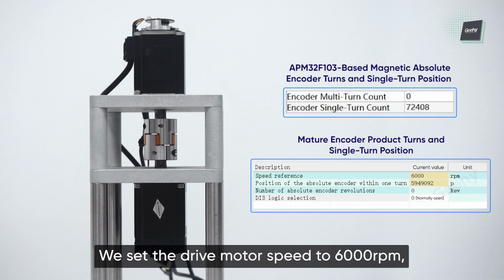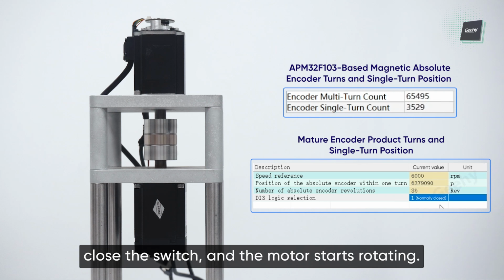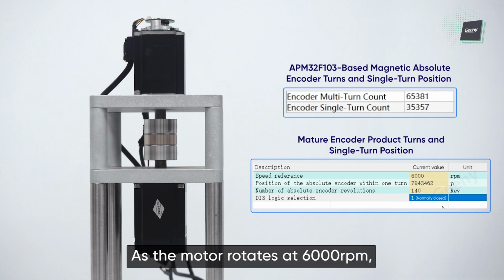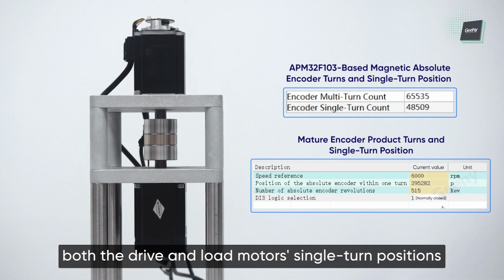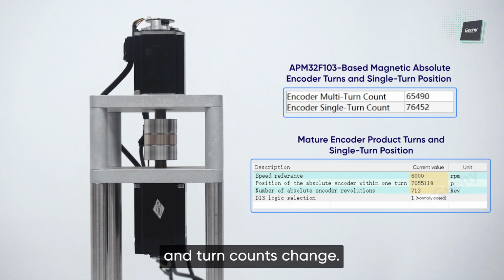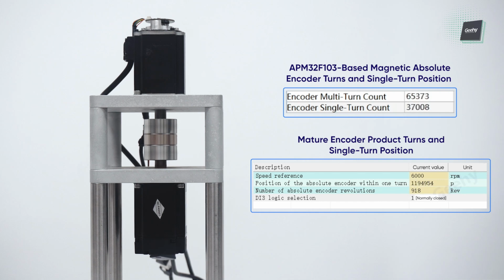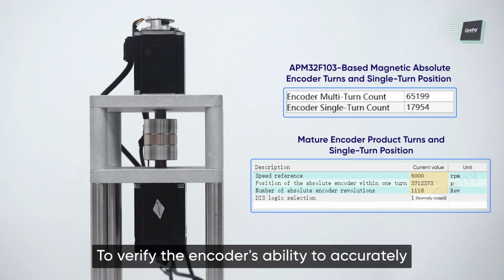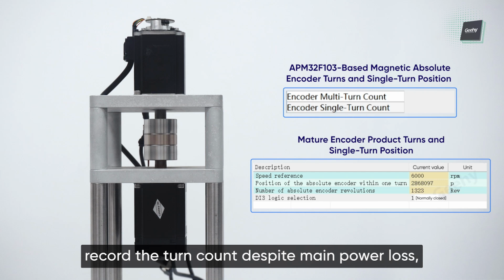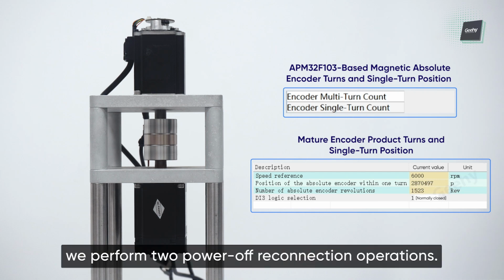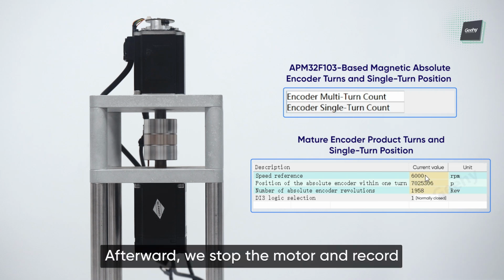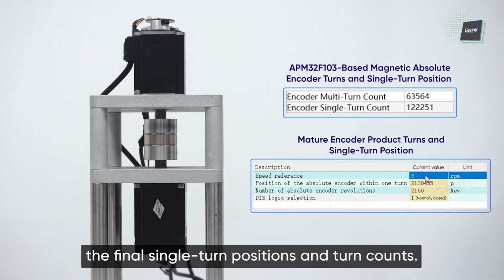We set the drive motor speed to 6,000 revolutions per minute, close the switch, and the motor starts rotating. As the motor rotates at 6,000 revolutions per minute, both the drive and load motors' single turn positions and turn counts change. To verify the encoder's ability to accurately record the turn count despite main power loss, we perform 2 power-off reconnection operations. Afterward, we stop the motor and record the final single turn positions and turn counts.